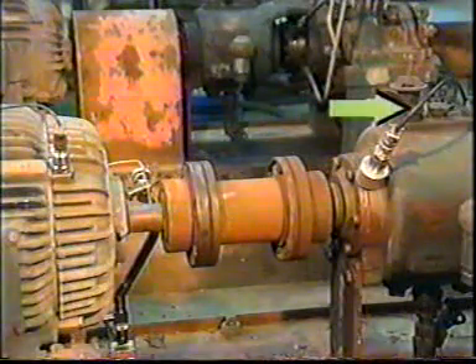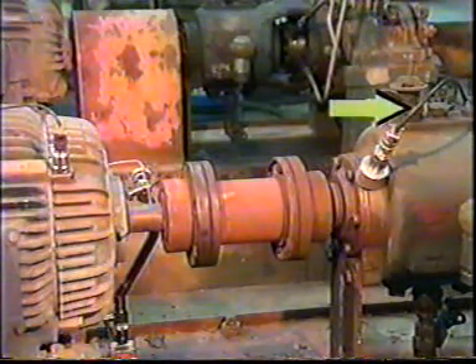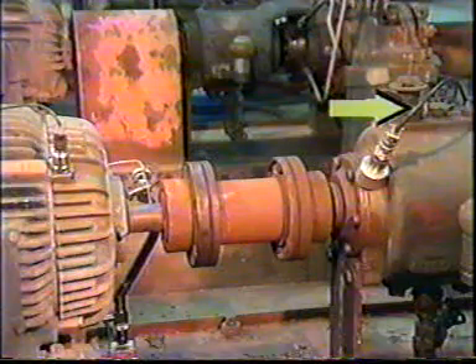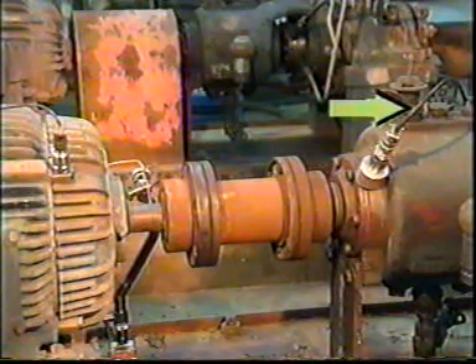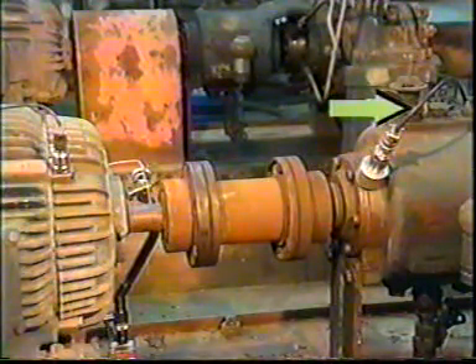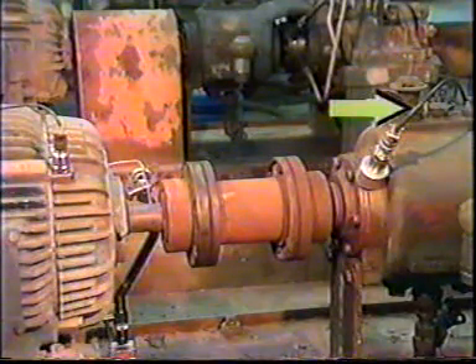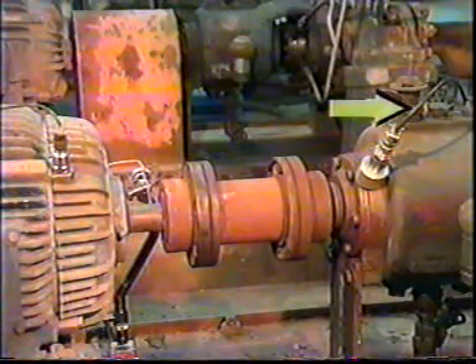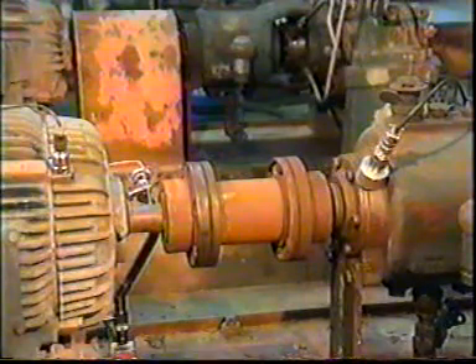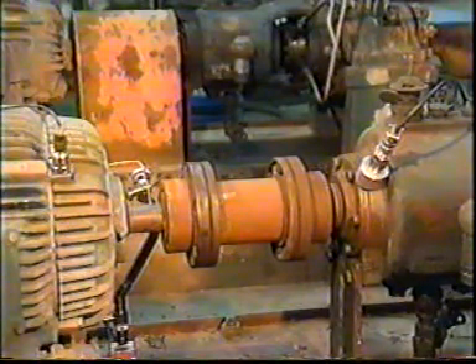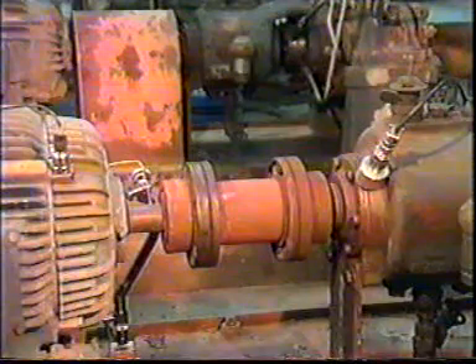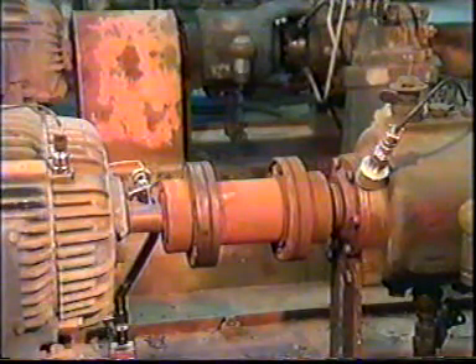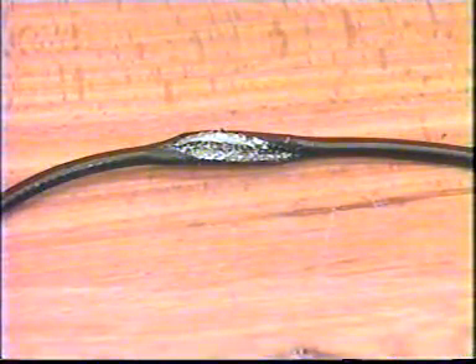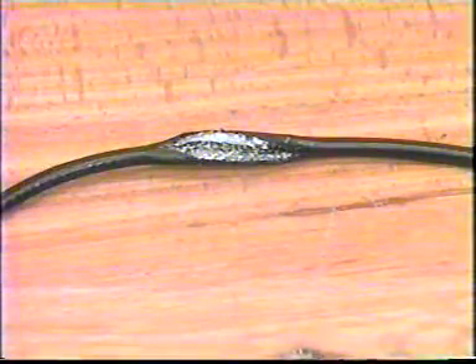Be careful with cables. Many times you may have temporary cables strung from your temporary sensors to an analyzer. Secure the cables to keep them from falling onto the rotating parts. Also, take care to keep cables off of floors. The cable is possibly the least expensive part of the vibration testing equipment, but it may cause the most problems due to erroneous signals. A crushed cable will cause bad signals, either with impedance problems or with stray signals.